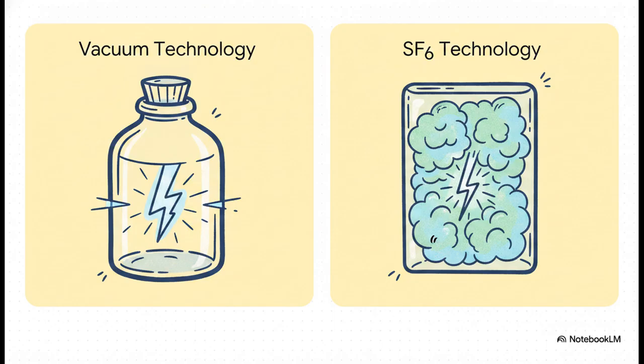On one side, we have vacuum technology. It's highly efficient, incredibly quick opening, and virtually maintenance-free inside its sealed bottle. On the other side, sulfur hexafluoride, or SF6 gas. It's odorless, colorless, non-toxic, non-flammable, and it boasts excellent heat transfer to quench that arc. Both get the job done, but they behave very differently when put to the ultimate test.